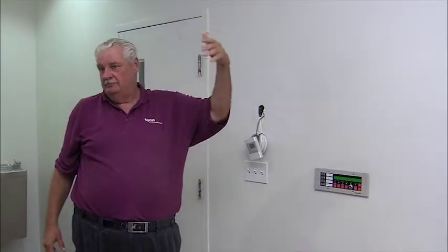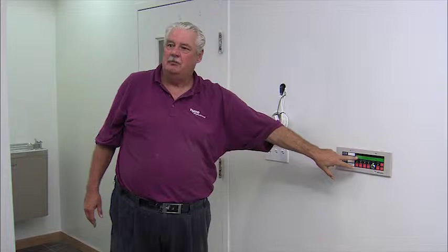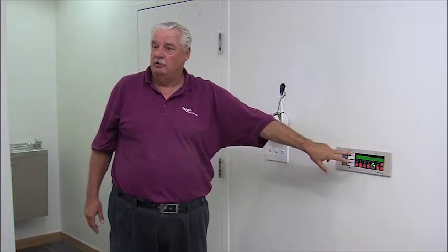After these detectors get some dirt through them, they go into a service mode, okay? And it lets the panel know that they're out of their adjusted frequency where they're supposed to be. Like right now it's blinking red. Should that be blinking? That's normal. They're never supposed to be green? No, ours don't have green on them. It's just one color. When it's solid red, that's when we have a problem. Solid red, it's either going to be an alarm or it's going to be dirty. You will see a trouble on the panel that says smoke detector dirty, okay?